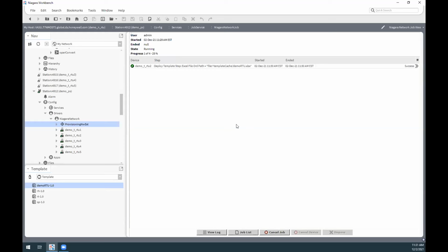As far as a template instance goes, that can also not be password protected. The internals are open and available to modify. We just are, as our tip, as you'll recall, we said you can't go in and modify that. And of course, Niagara protects any sensitive data like passwords that might be in them already, so those would not be exposed. But as I said, you can encrypt a template configuration Excel spreadsheet file because it uses Excel's encryption and password protection so that you can protect the contents of that configuration.